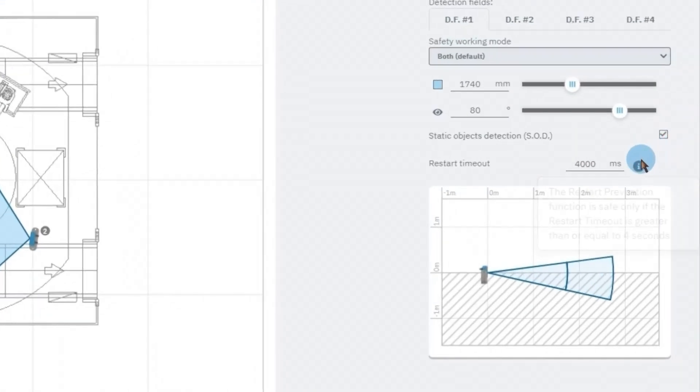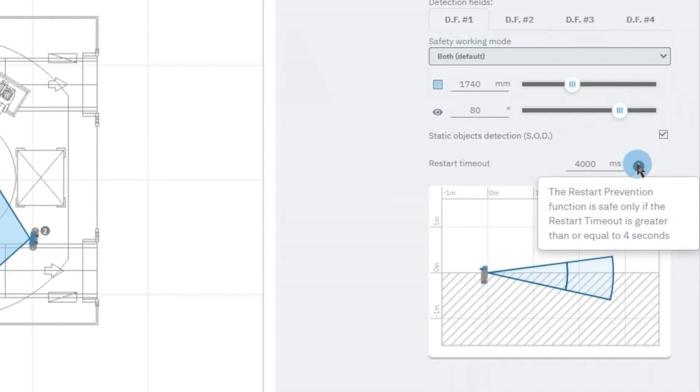Remember that for the SmartSensor 200 series the restart prevention function is deemed safe only with timeouts of four seconds or longer.